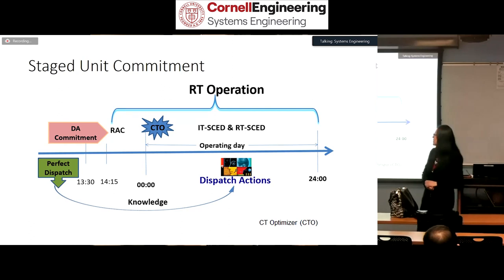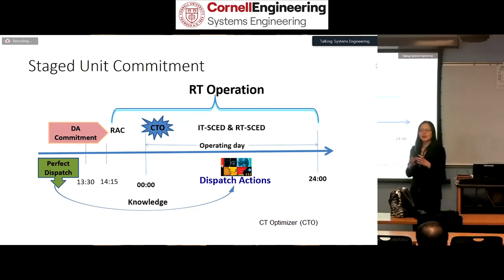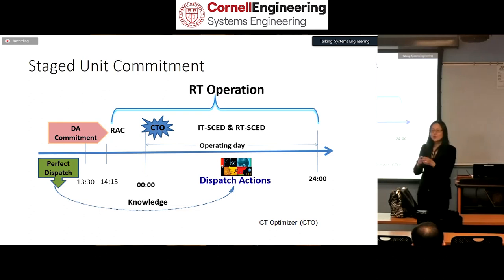When we do this security-constrained unit commitment problem, we base it on forecast load, so ideally we have power balance—exact generation megawatts need to meet the load. However, this is all based on bid price, and since those generators represent a non-convex problem, especially the big ones, they have their increment. So if we call you online, you can't stay at a random megawatt—at least if you're online, you have to stay at your increment.